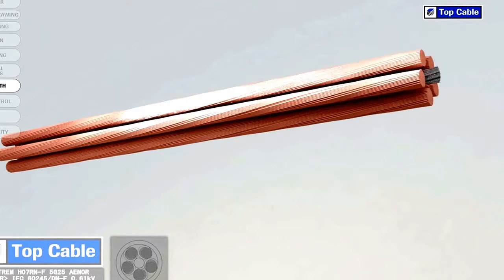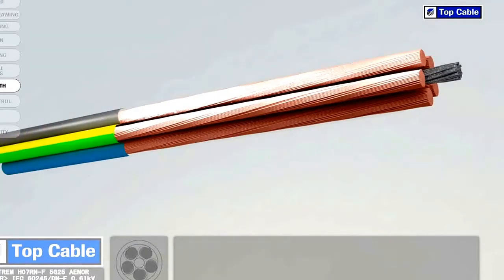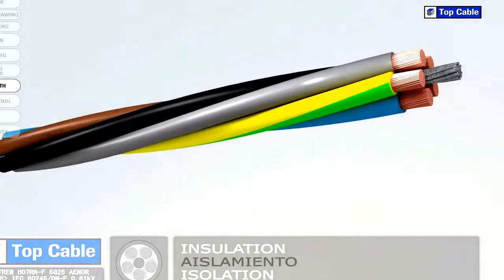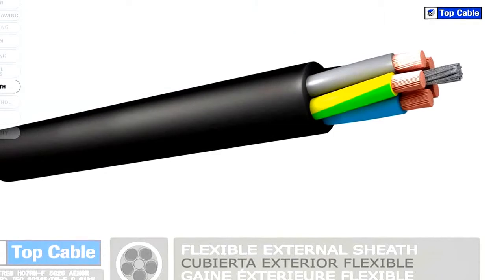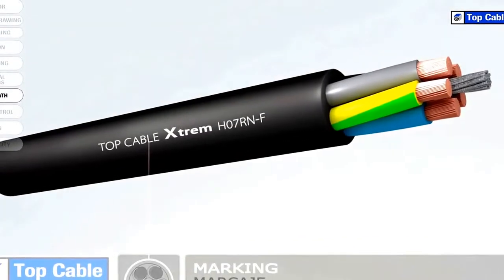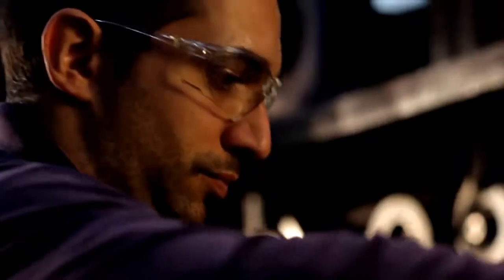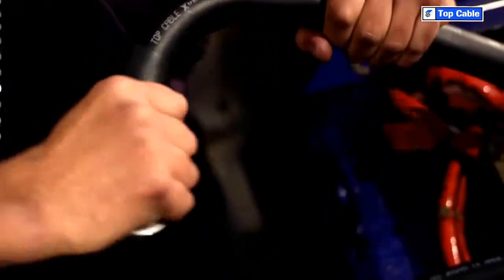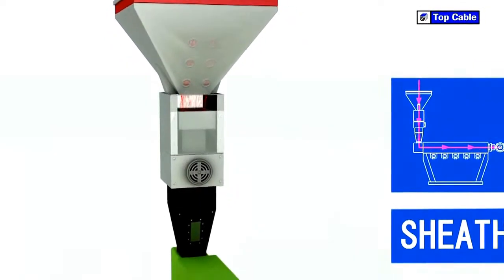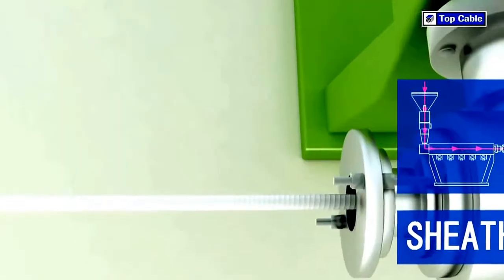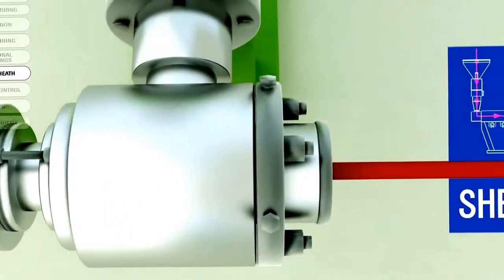Cables usually have an outer polymer covering for protection, called the outer sheath. The sheath protects the conductors and their insulation from external elements which may change their electrical properties, such as moisture. It also protects them from mechanical aggression which may occur during installation. As with the insulation, the outer sheath can be made from a thermoplastic or a thermosetting plastic, applied via a process of extrusion at high temperature. The sheath material varies depending on the required protection level, final flexibility, and work environment.